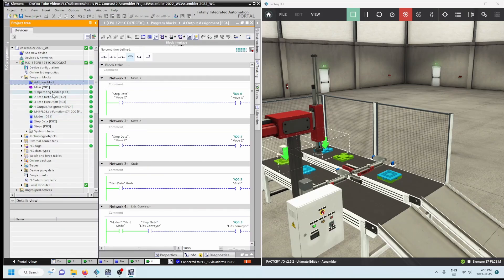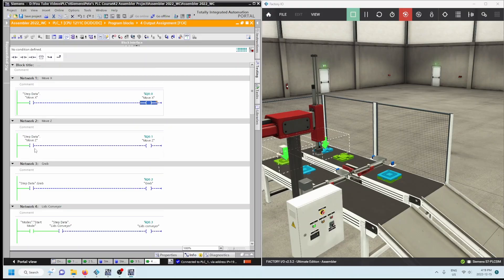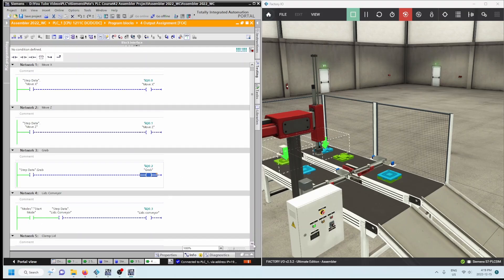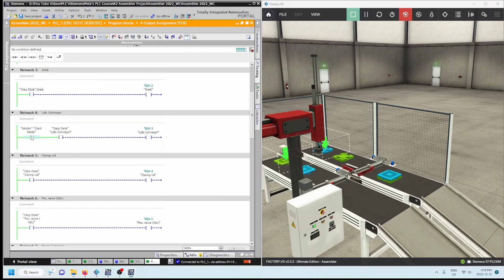Separating everything into functions really simplified my program. I did my operating modes, defined each step, did the step execution — which was probably the hardest because of timing — and step definition was difficult too. But timers were needed in step execution. The output assignment was the easiest part: when this is true this is on, when this is true this is on. For grab: step data 'grab' is true, grab is on at Q0.2. For lids conveyor: start mode is true and lids conveyor is true in step data, then turn on Q0.3.